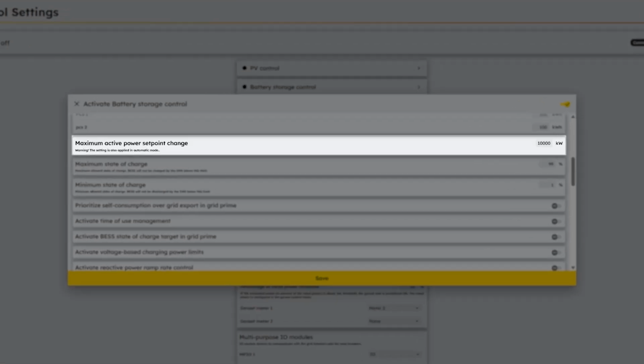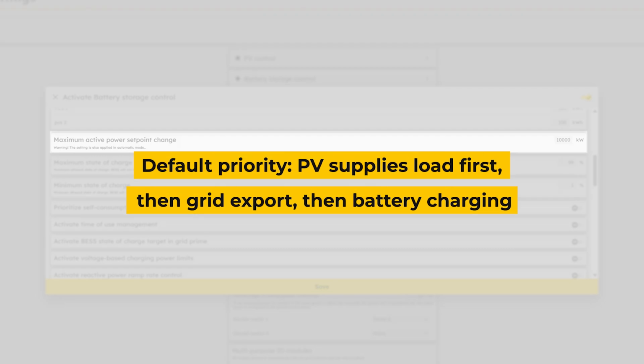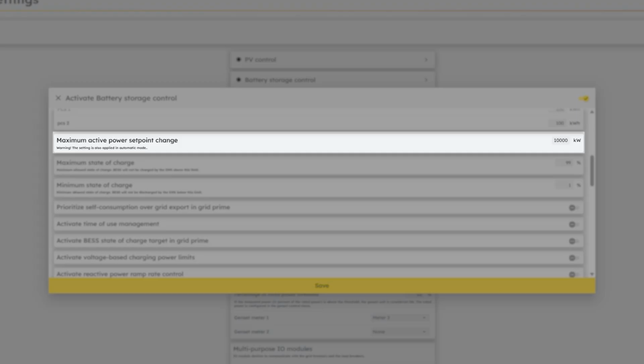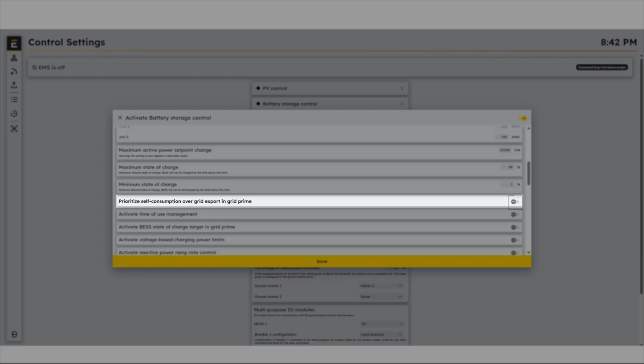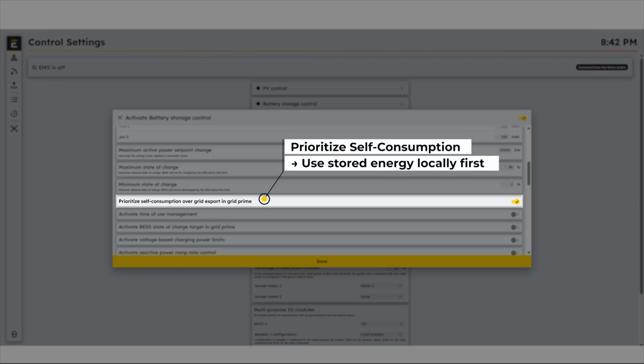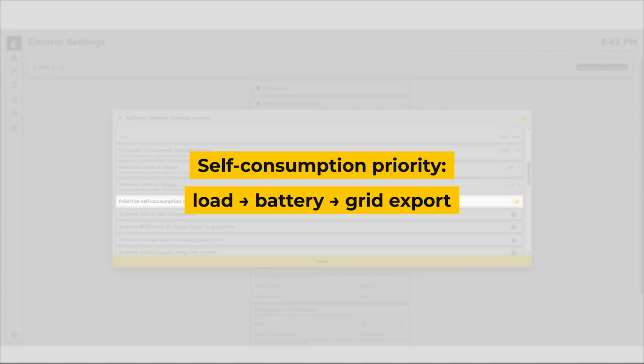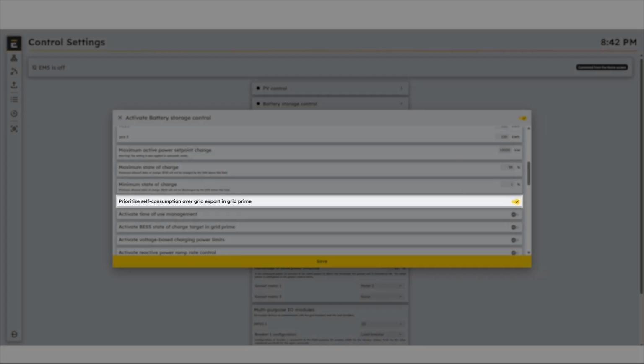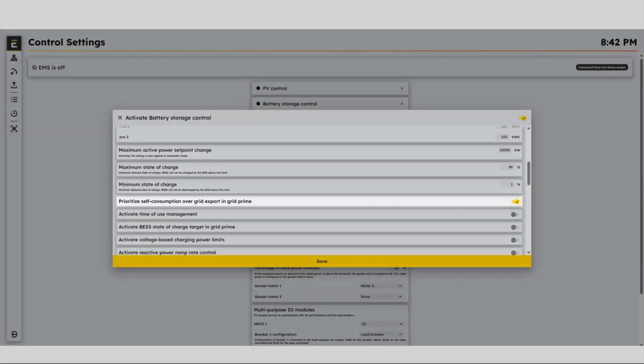By default, the EMS prioritizes using PV production to supply the load first, then export excess power to the grid, and finally store any remaining surplus in the battery. When self-consumption priority is enabled, this logic changes. The EMS will feed the load first, charge the battery second, and only inject any remaining power into the grid. This mode helps maximize on-site renewable energy use and reduce grid dependency.